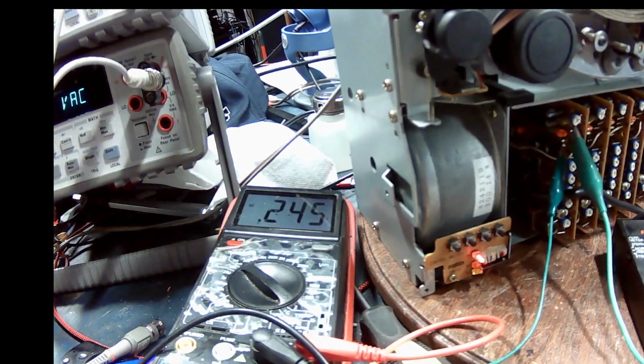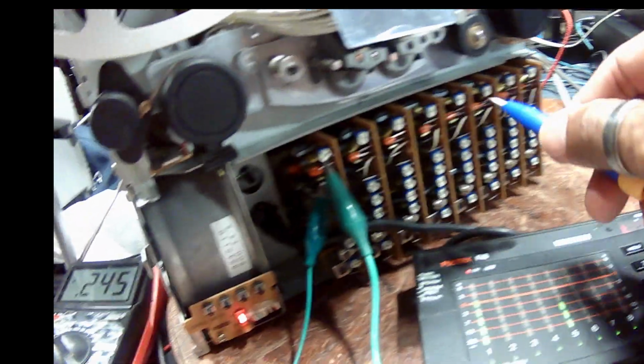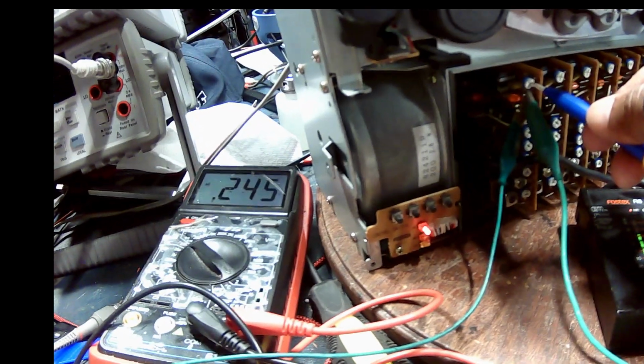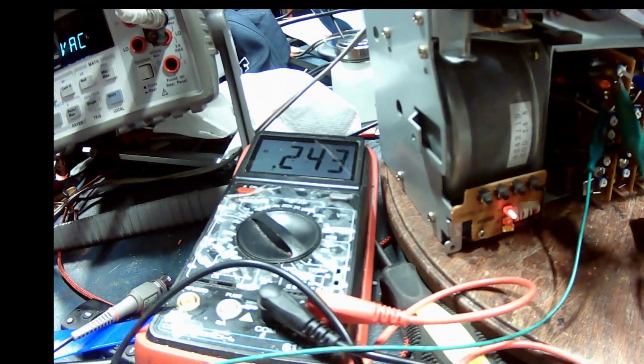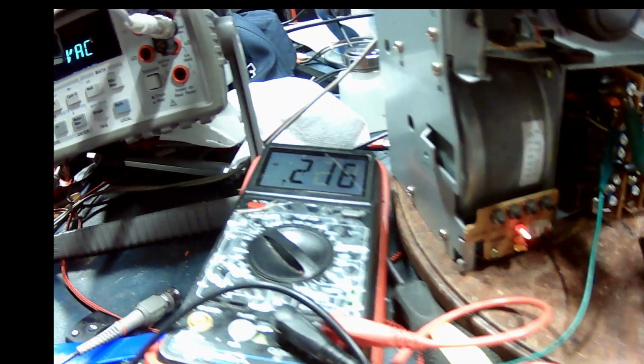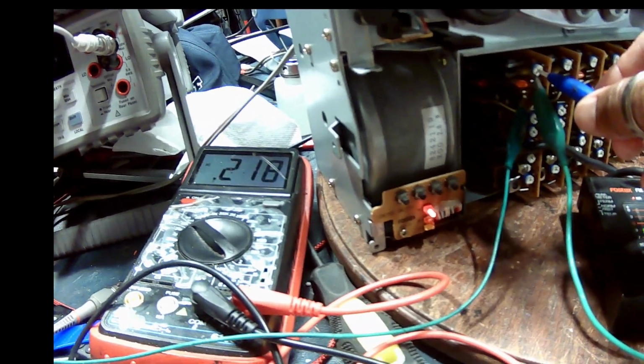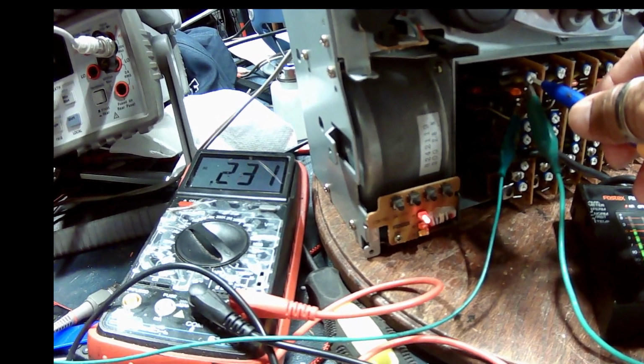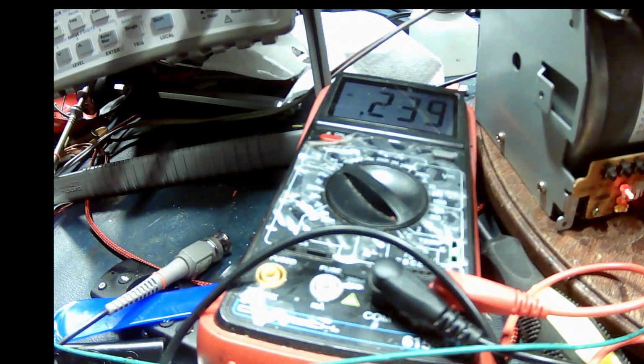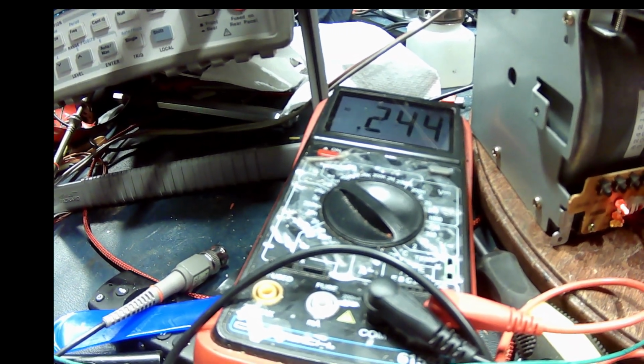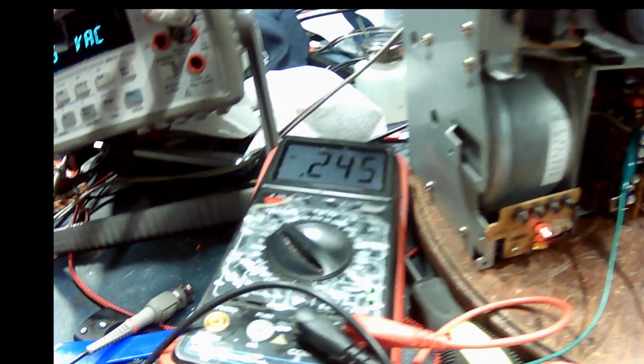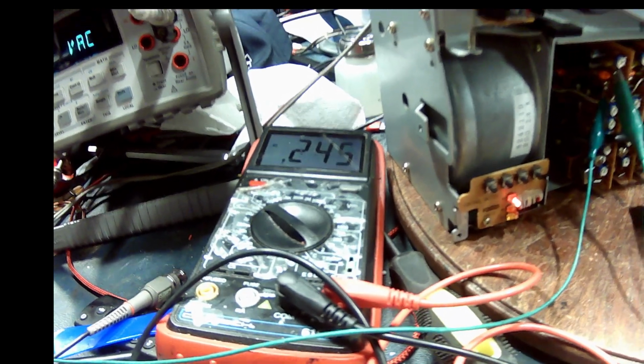Okay, and the next step, you do the same thing on all 8 channels. Again, if your reading's a little bit low, let's say it's down to 210 or whatever, all you do is rotate this potentiometer clockwise until you get up to 245. And that's it for that part of the calibration.